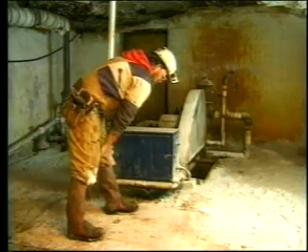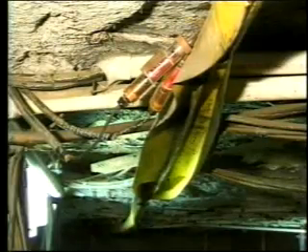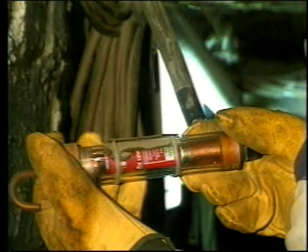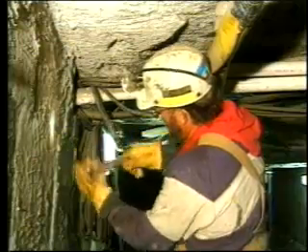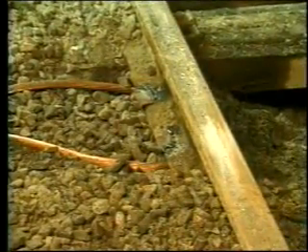A dewatering pump is another common type of DC equipment found in an underground mine. A DC pump receives its electrical power by attaching a device called a nip to the trolley wire. The nip contains a fuse of the correct size, type, and rating for this particular application. Make certain an ID tag is attached that identifies which piece of equipment the nip supplies power to. The power cable for the nip must be adequately insulated and fully protected. The frame ground and return wires must be attached separately to the mine track and solidly connected.